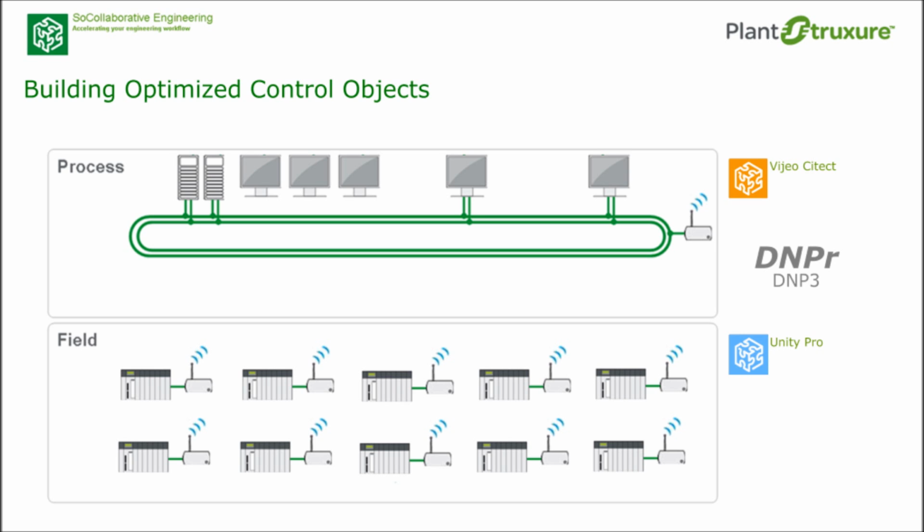The report by exception and event buffering features enable real-time alarm transmission and trend backfill as a part of the protocol, requiring no programming in the RTU to implement these functions. Taking advantage of these is another way to keep your hands off the keyboard and further optimize the efficiency of delivering a PlantStruxure solution.